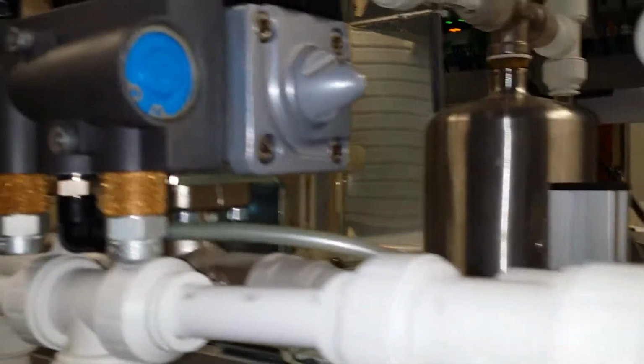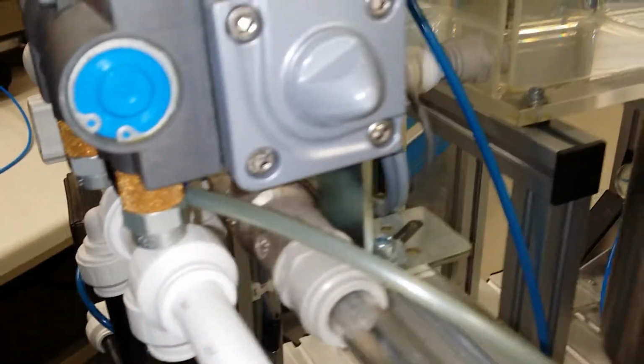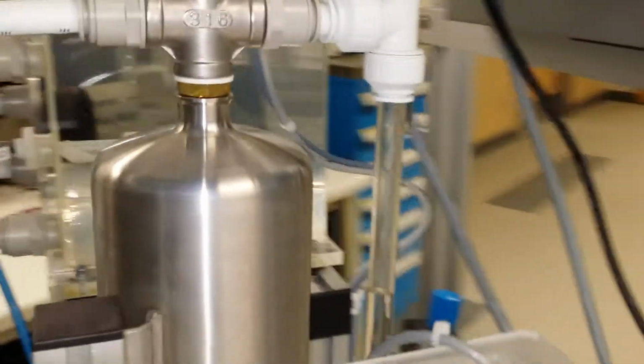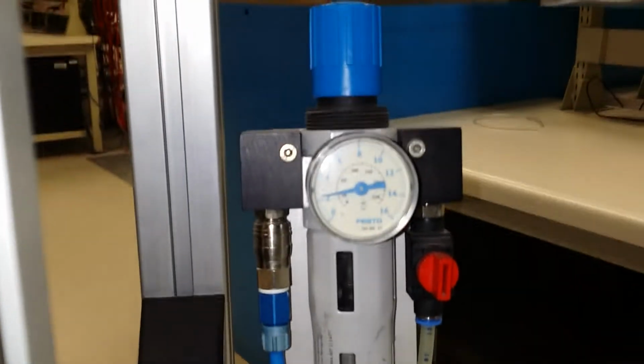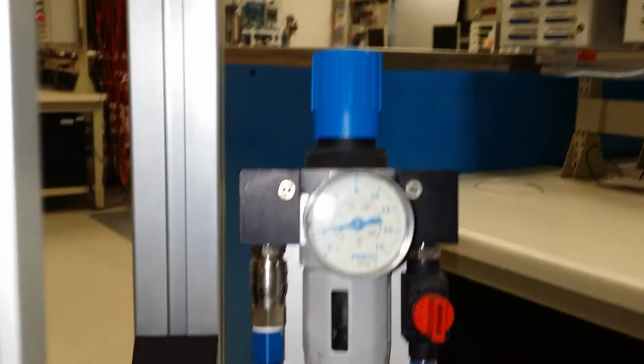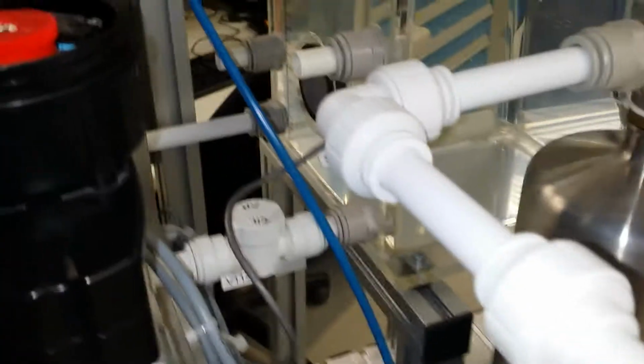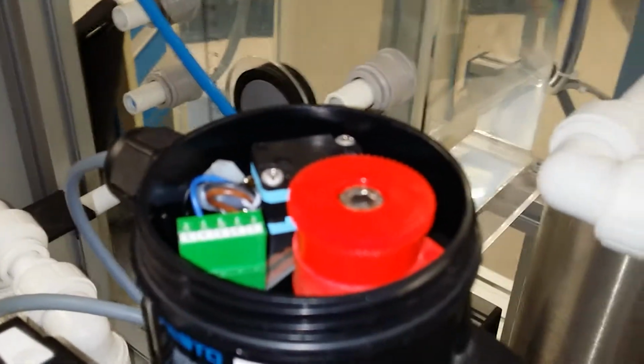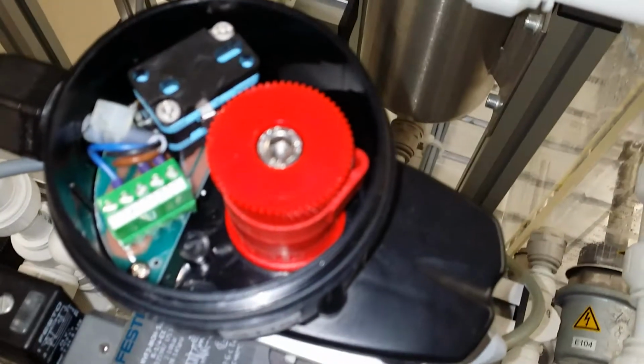You can see to operate the ball valve, it requires an electrical signal and a pneumatic signal. The pneumatics comes from down here. Okay, and I think you can see the pressure. The pressure should be around 2 bar. It's hard for me to see that right now. Okay. And I want to show you the ball valve operating, so I'll remove this. And it's going to be a little bit tough for me to move the controls and show you the ball valve, but I'll show you the current position.